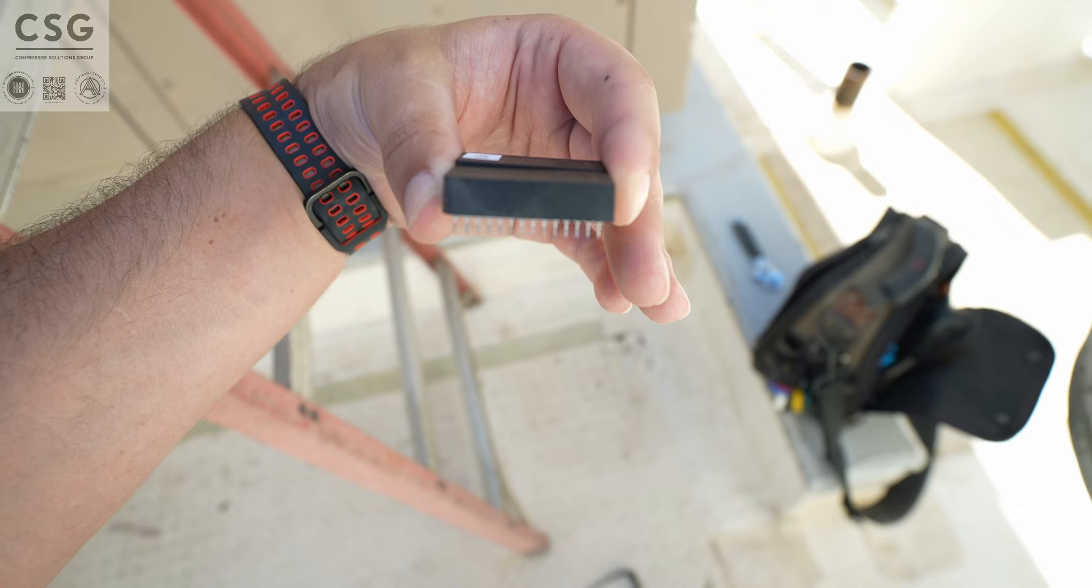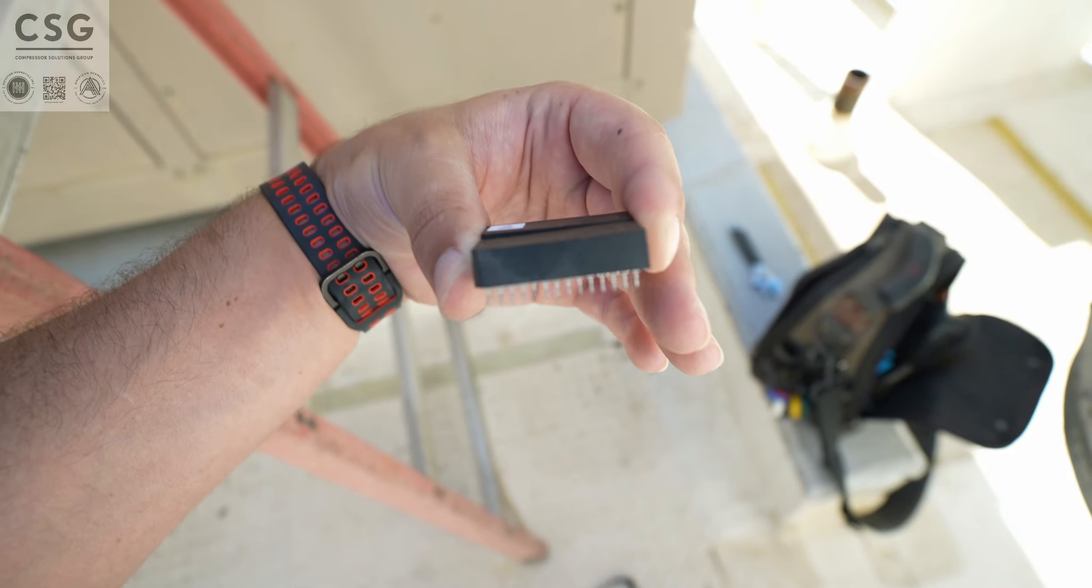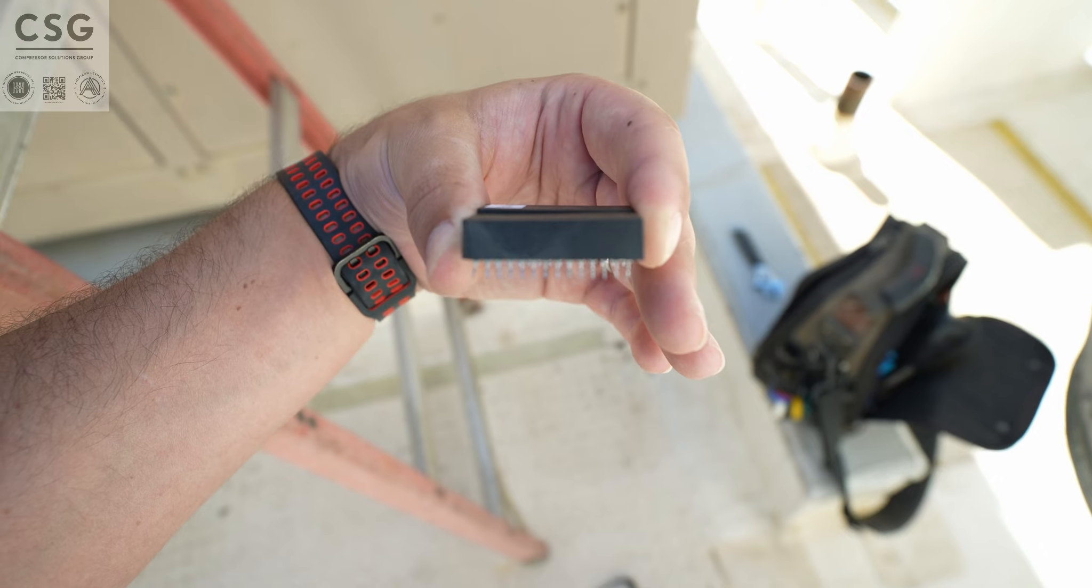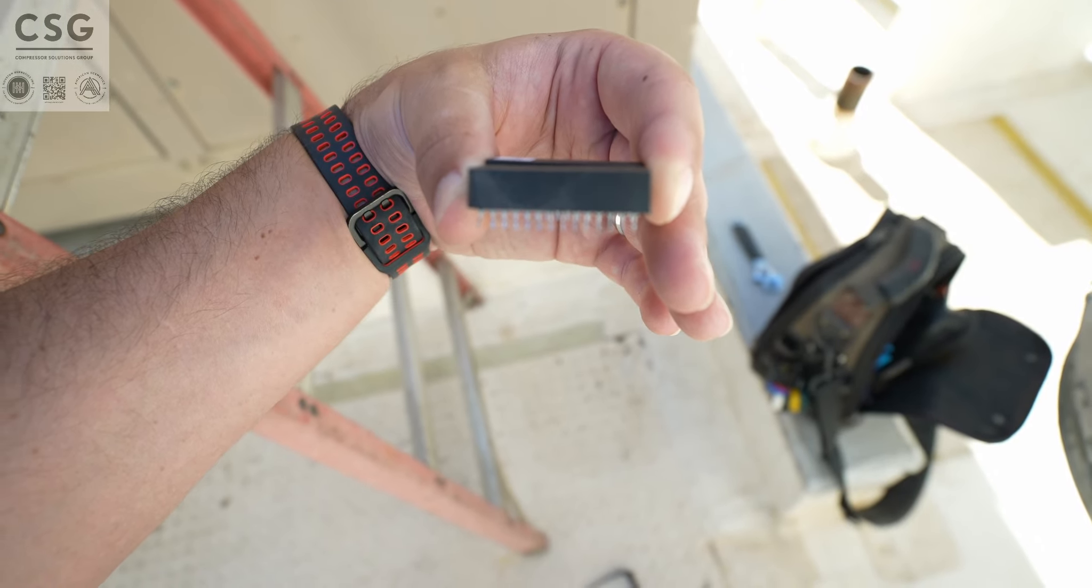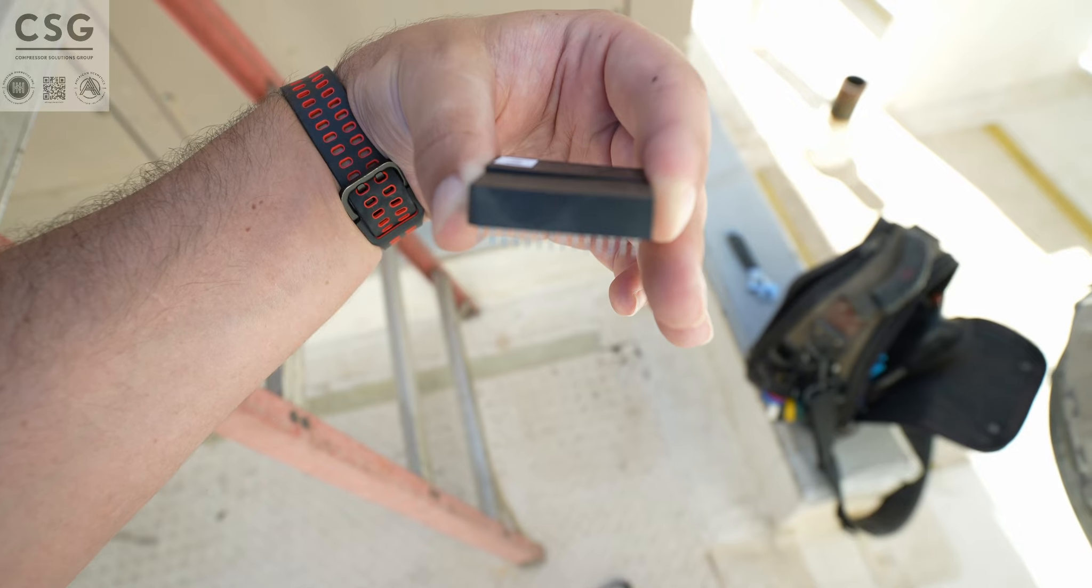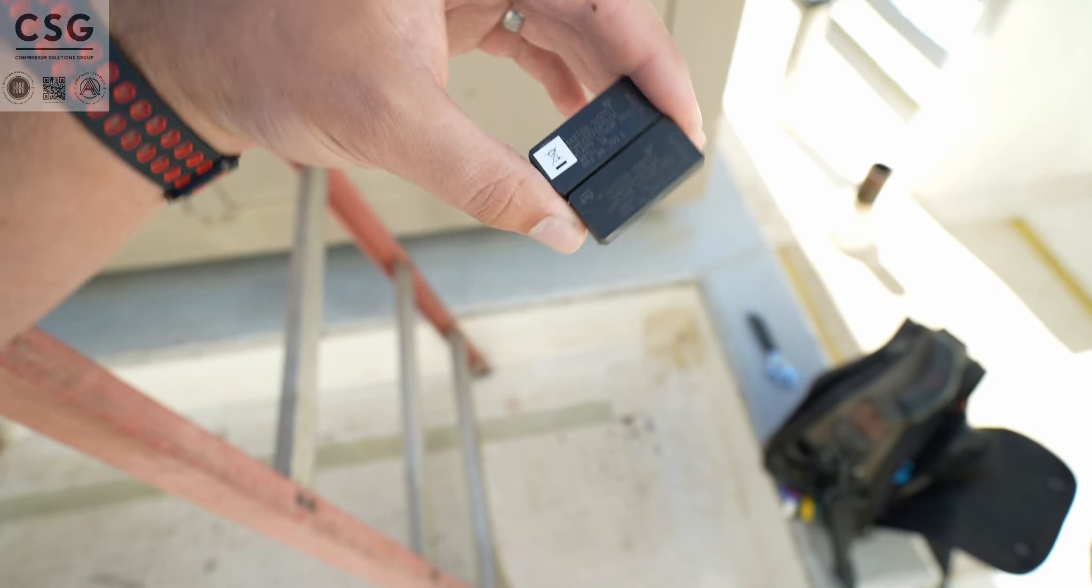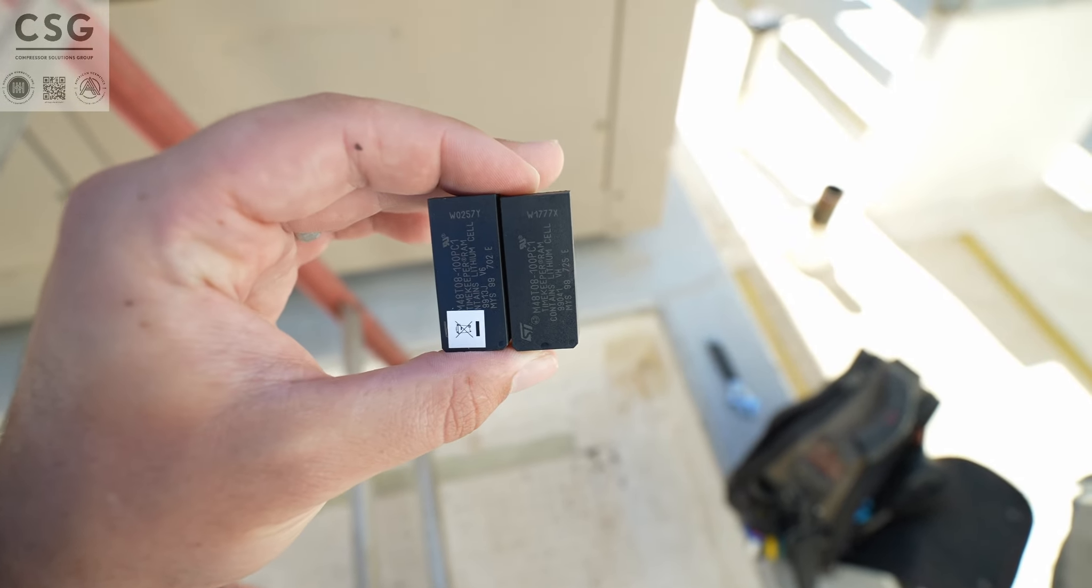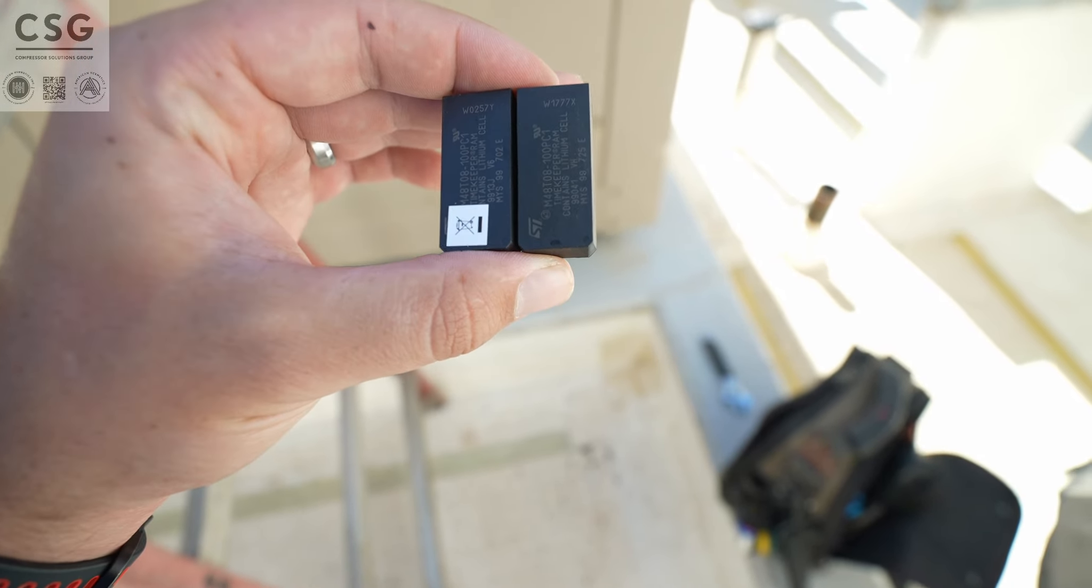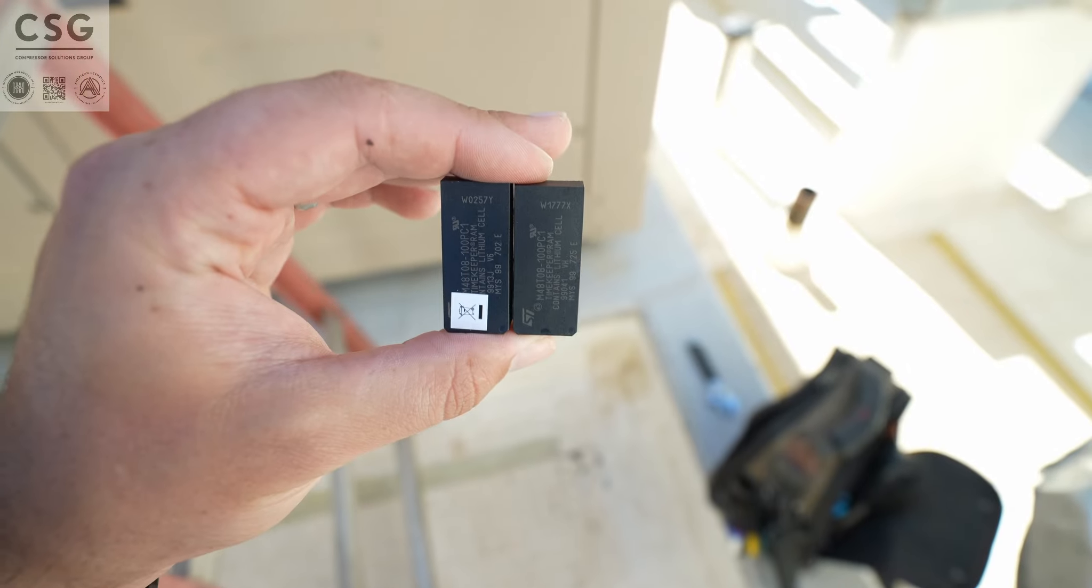I don't know how well this is going to capture, but if you look, the one without the white tag is the old one and it's just ever so slightly bulged on the right side there. That is where the battery sits. Now the other thing - these go in a very specific way. If you notice, one side has harsh corners, the other side has cut corners. Gotta make sure you pay attention to which is which.